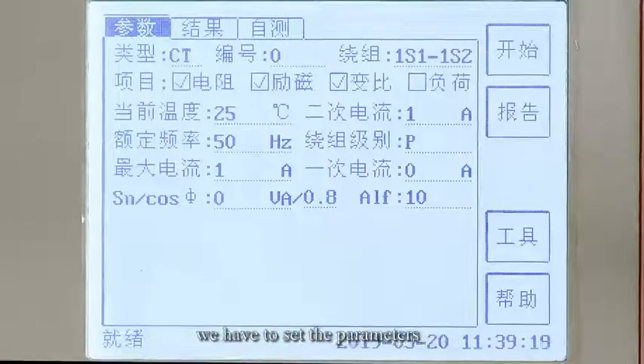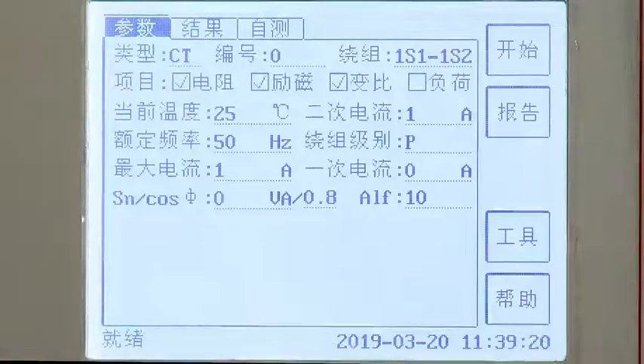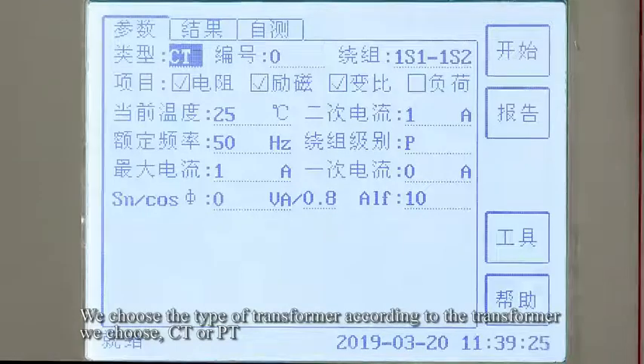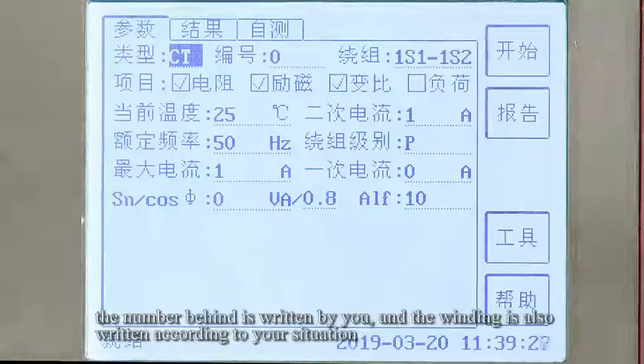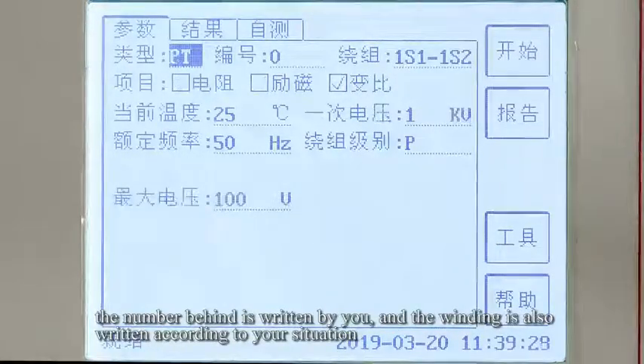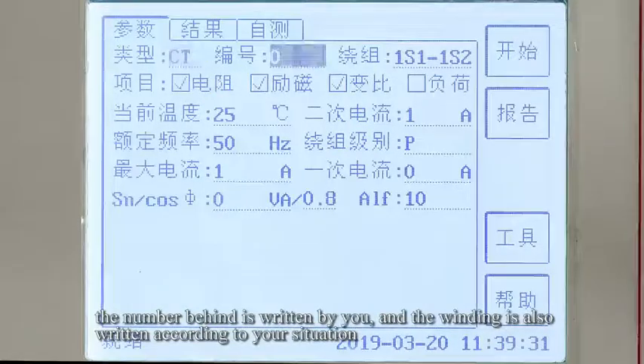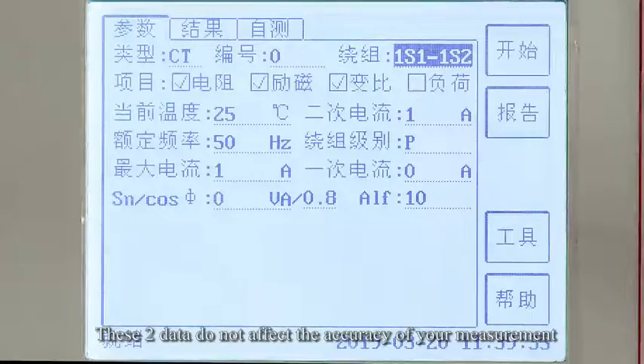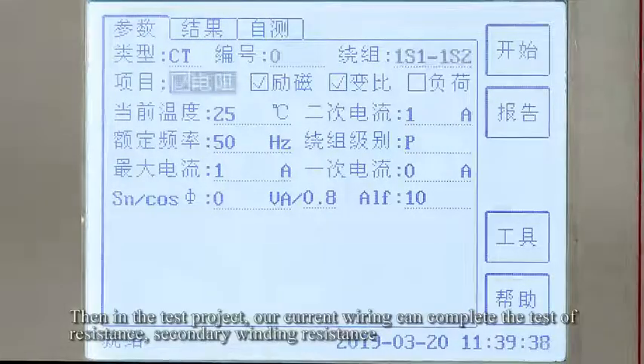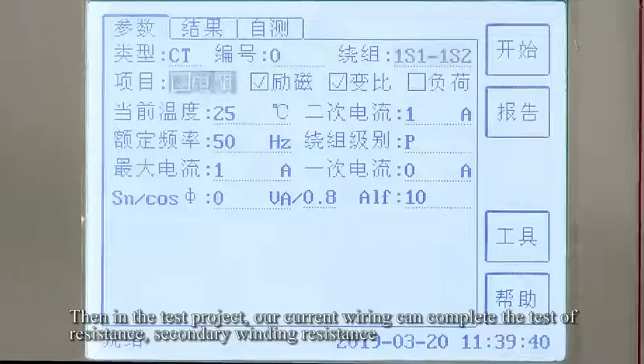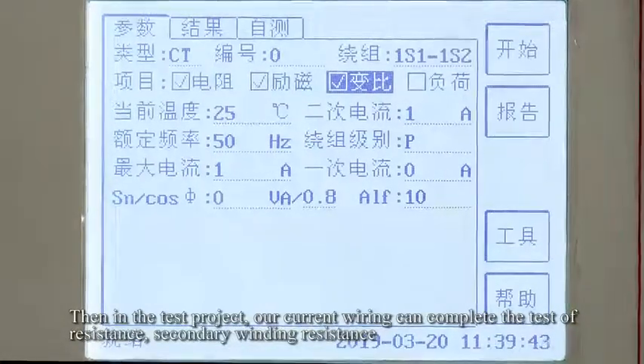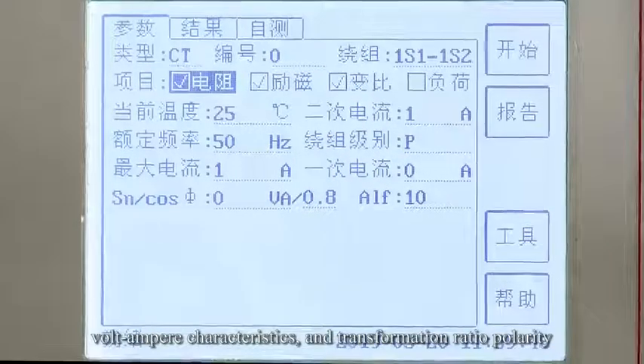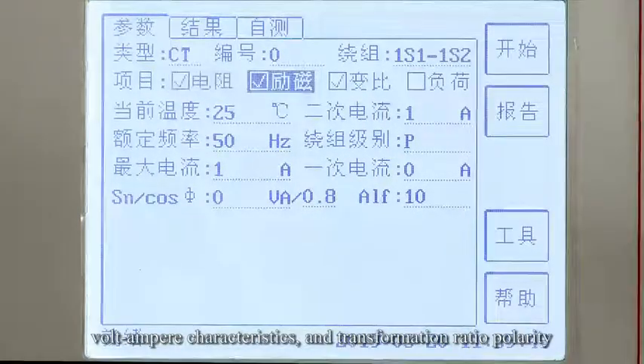After we first turn on the power, we have to set the parameters. We choose the transformer type — CT or PT. The number and winding fields are filled in according to your situation. These two data do not affect the accuracy of your measurement. Then, in the test project, our current wiring can complete the test of resistance, secondary winding resistance, volt-ampere characteristics, and transformation ratio polarity.